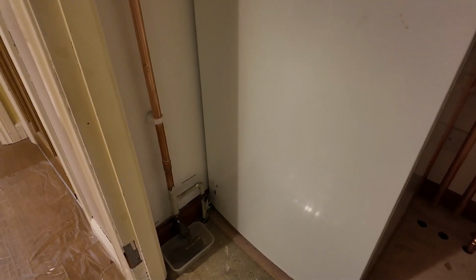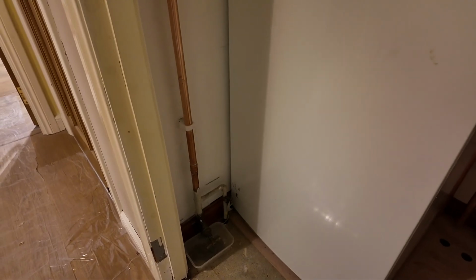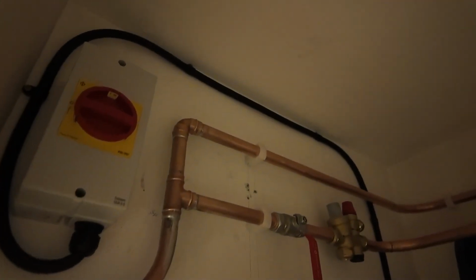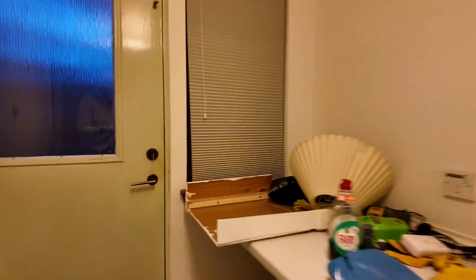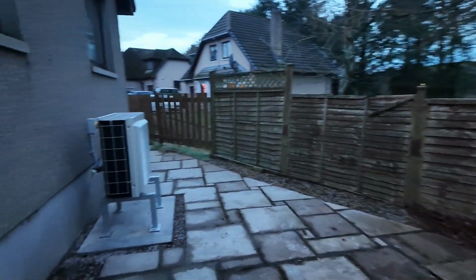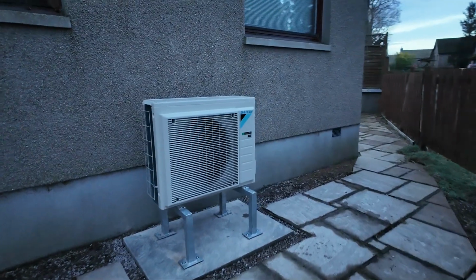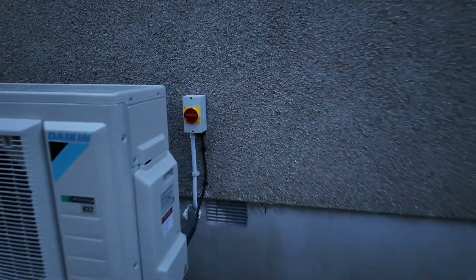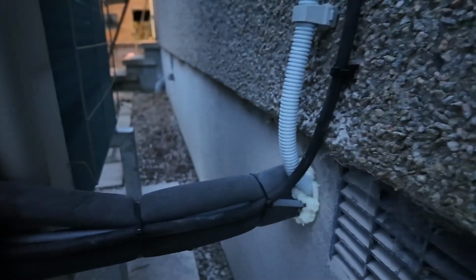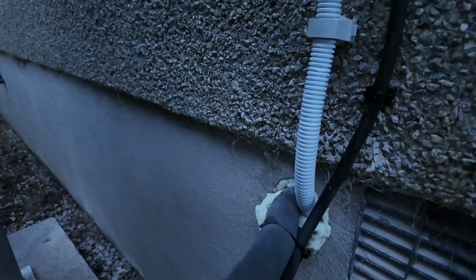That's the main inlet valve. There's a packing nut which is leaking. So that needs to be replaced. I think it's looking like a nice tidy job in here. So let's go through to the outside. So here's the heat pump. It's not too big at all. And we've got this enclosure here. You can see we've got the cabling. We've got some sealant around, expanding foam around the penetration into the wall.